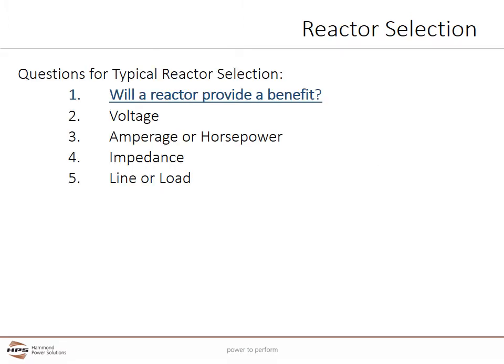There are five main items needed for line reactor selection. Number one, will a line reactor provide a benefit? This is different from asking does a VFD need a reactor. We also need to determine the voltage of the VFD and motor, the amperage or horsepower required, the impedance which is typically measured as a percentage, and whether this is a line or input side reactor or a load or motor side reactor.